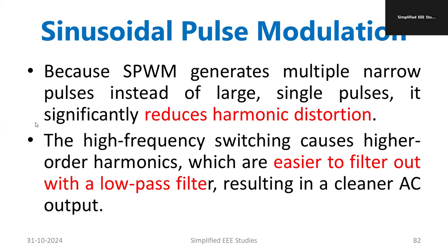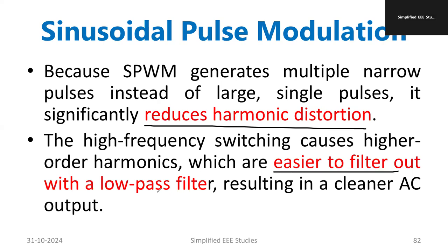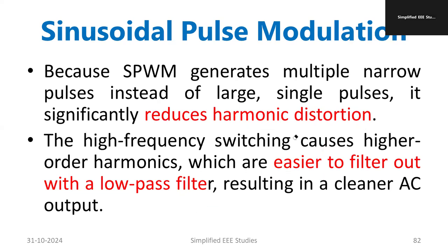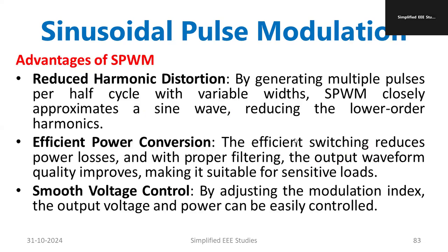The most important thing to remember is that there is a reduction in harmonic distortion, because more number of pulses are generated at each cycle. Therefore, lower order harmonic presence can be minimized. The remaining harmonic content can be easily filtered out using a low pass filter. The design of the low pass filter is not very difficult to manage.